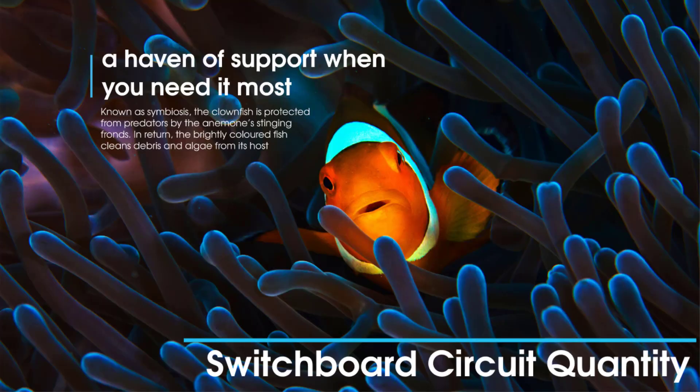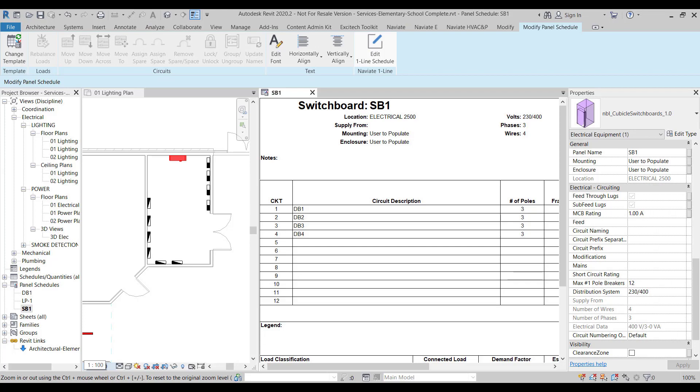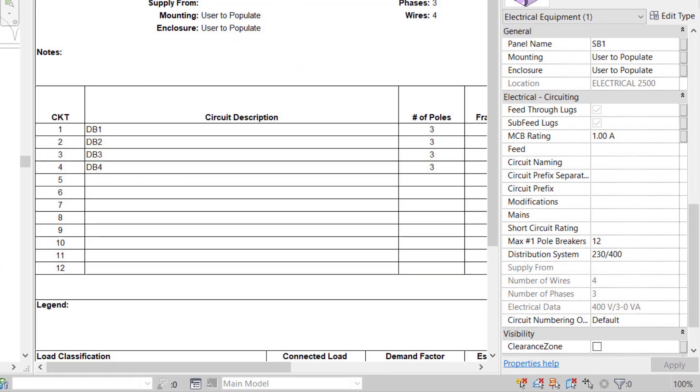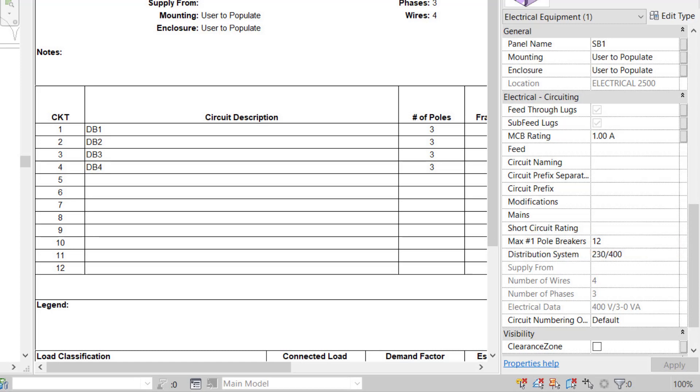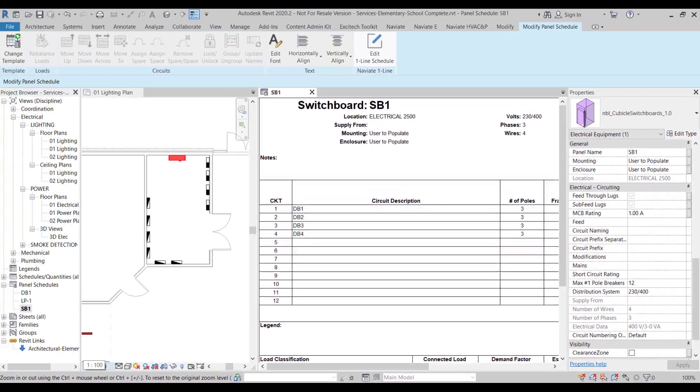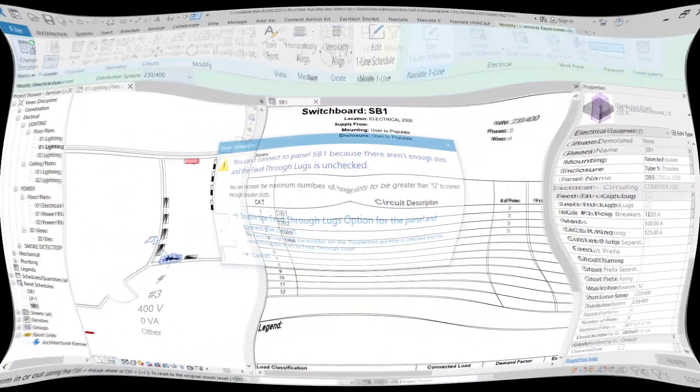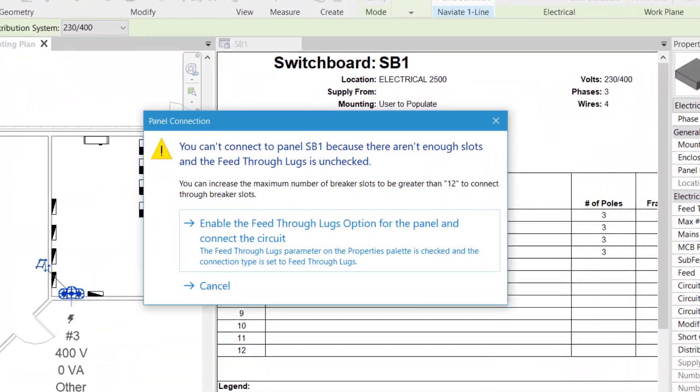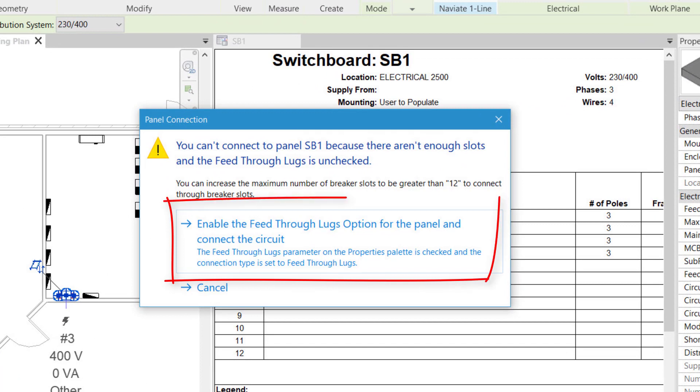The next feature we'll take a look at is switchboard circuit quantity. Prior to the 2021 release of Revit MEP, elements identified as either switchboards or panel boards had a property called maximum number of single pole breakers. This property determined the number of slots available within the respective board. For panel boards this wasn't a problem as a three-phase circuit would show as taking three slots. However on a switchboard schedule, a three-phase circuit would only show as occupying a single slot, giving the appearance of available capacity, and if that capacity was exceeded the user would receive an error message.